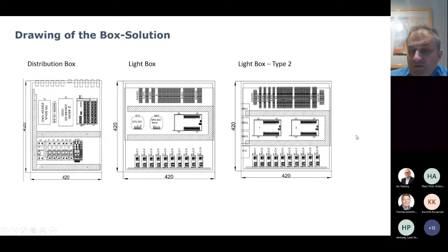What is important to the configuration of this is that the complete hotel runs one big fat network, and every application is running in its own virtual network. For example, the room automation has its own virtual network, the access points for WLAN run in a separate virtual network. The connection to the hotel management system is also another virtual network.